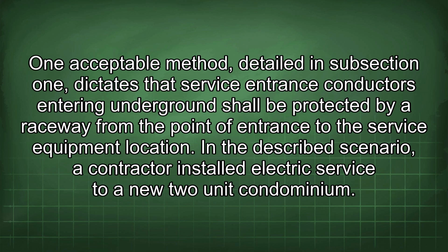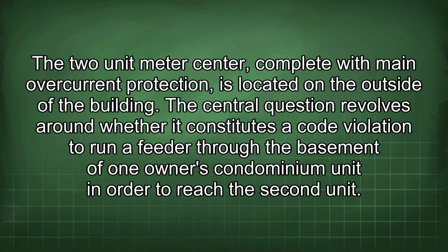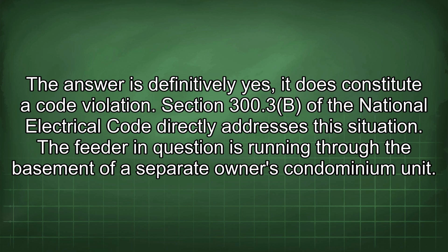In the described scenario, a contractor installed electric service to a new 2-unit condominium. The 2-unit meter center, complete with main overcurrent protection, is located on the outside of the building. The central question revolves around whether it constitutes a code violation to run a feeder through the basement of one owner's condominium unit in order to reach the second unit. The answer is definitively yes, it does constitute a code violation.